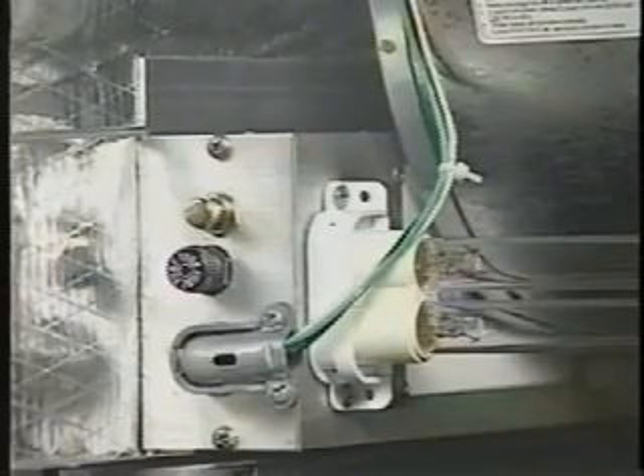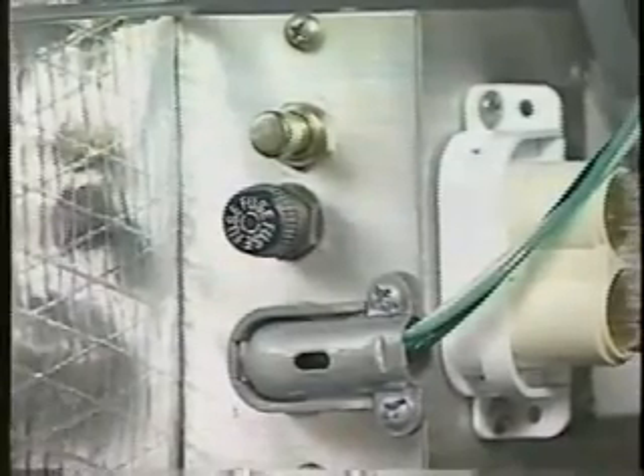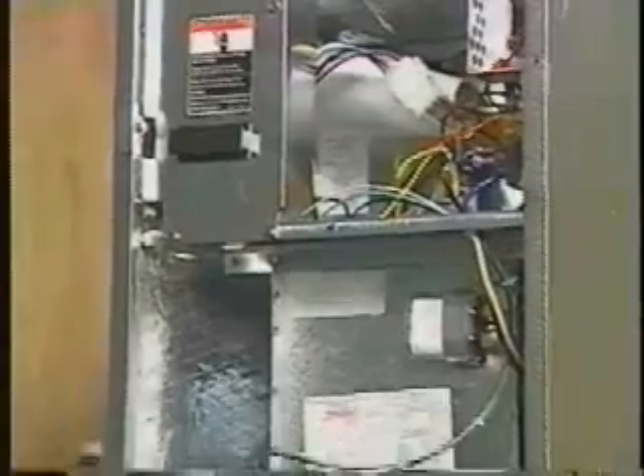We have another type that looks very similar to this, but the controls are on the back of the unit, so that if your coil is at the top of the air handler instead of in the bottom, you can just cut a hole in the ductwork and install it that way. It is just this easy. Taking the fan out and putting the covers on is probably the hardest part of this installation.